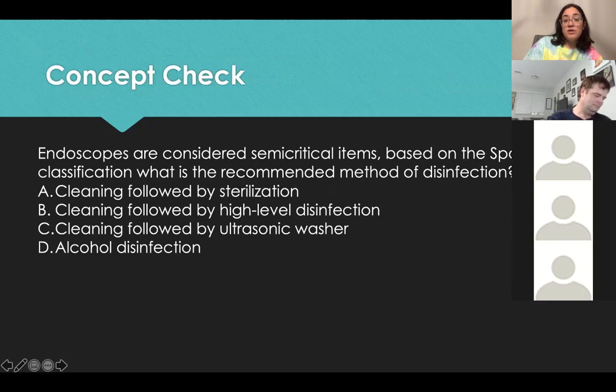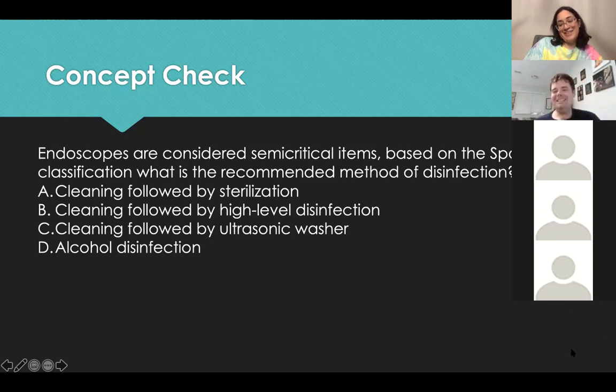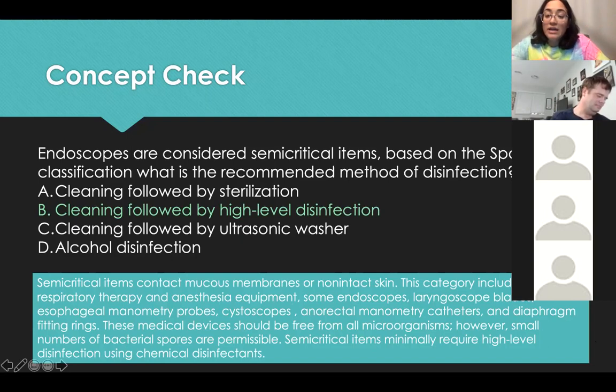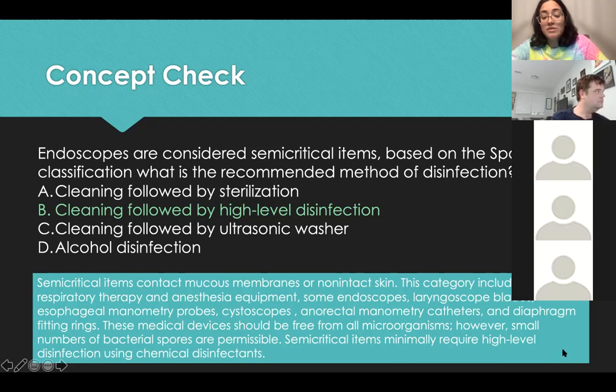Concept check: endoscopes are considered semi-critical items based on the Spaulding classification. What is the recommended method of disinfection? Cleaning followed by high-level disinfection. Semi-critical items include respiratory therapy and anesthesia equipment, some endoscopes, laryngoscope blades, esophageal manometry probes, cystoscopes, and diaphragm fitting rings. These devices should be free from all microorganisms, though small numbers of bacterial spores are permissible. Semi-critical items minimally require high-level disinfection using chemical disinfectants.